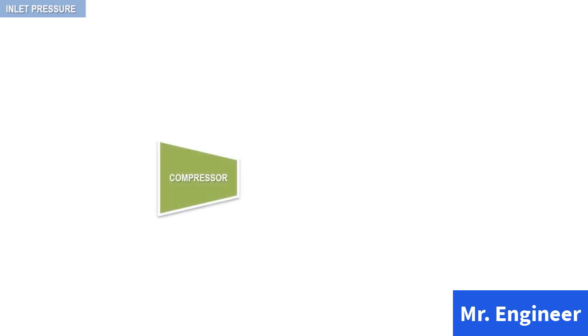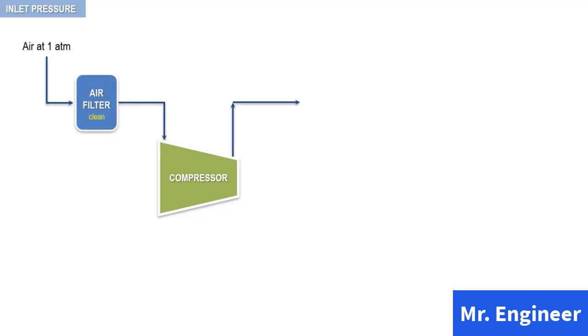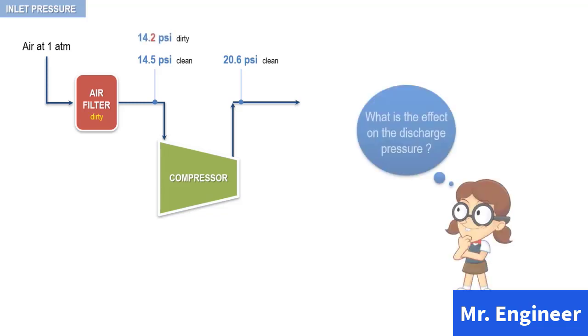Let's begin by considering the effects of a variation in inlet pressure. Consider that the following compressor draws atmospheric air through an inlet filter. The rated compressor inlet pressure is 14.5 PSI. The discharge pressure in this case is 20.6 PSI. When the filter becomes dirty, the inlet pressure at the compressor flange drops to 14.2 PSI. What is the effect on discharge pressure and shaft horsepower at the rated inlet volume flow?